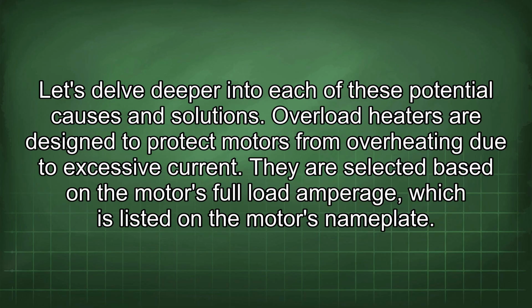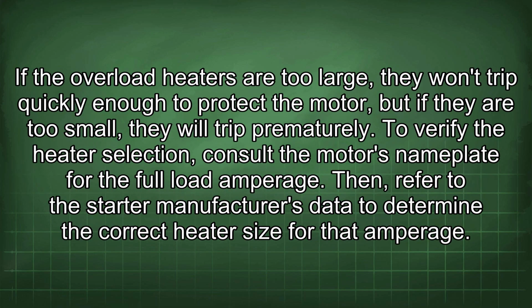Let's delve deeper into each of these potential causes and solutions. Overload heaters are designed to protect motors from overheating due to excessive current. They are selected based on the motor's full load amperage, which is listed on the motor's nameplate. If the overload heaters are too large, they won't trip quickly enough to protect the motor, but if they are too small, they will trip prematurely.